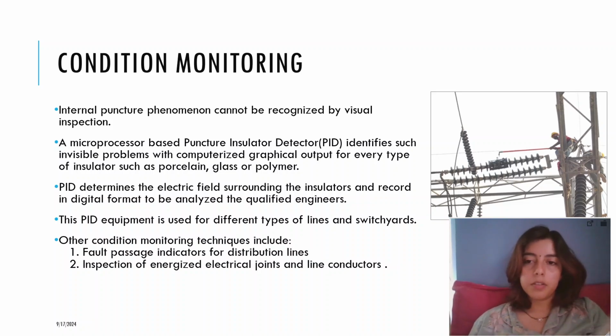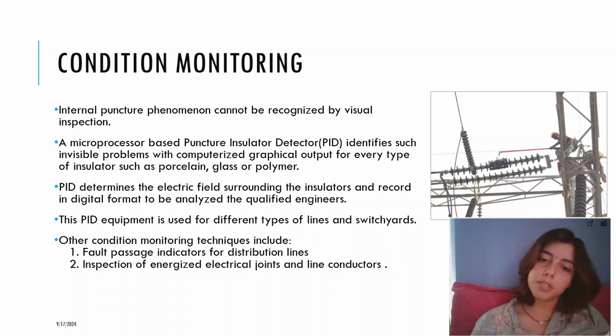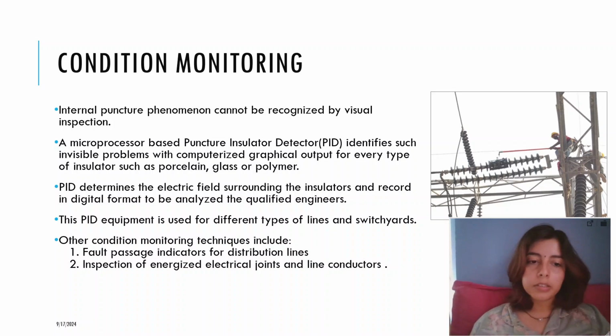This is done for every type of insulator, such as porcelain, glass, or even polymer insulators, used for different types of lines and switch yards. In switch yards you will have these insulators, and in transmission lines too. This is one example where we monitor the condition of the system while it is still energized, while still being supplied electricity.